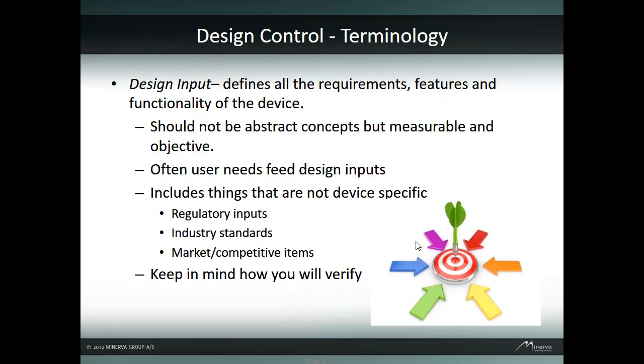Design input defines all the requirements, features, and functions of the device. Unlike user needs, design inputs need to be objective and measurable. Some of the design inputs are typically derived from user needs. Design inputs don't all need to be device-specific since they can also come from regulations, industry standards, and even market and competitive needs. When defining design inputs, always keep in mind how you will verify them, since verification is an important step in design control.